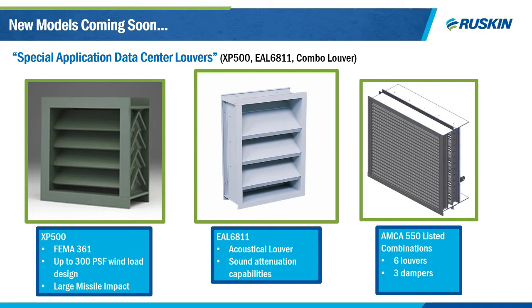So this is important because a lot of data centers are located near either residential areas or business districts. And in these settings, the data centers must be designed to assure that the generator noise is not emitting noise pollution into those areas. You know, you get angry residents, angry business professionals. So for that improved sound attenuation, the EAL 6811 is the choice for acoustical louvers in a data center.